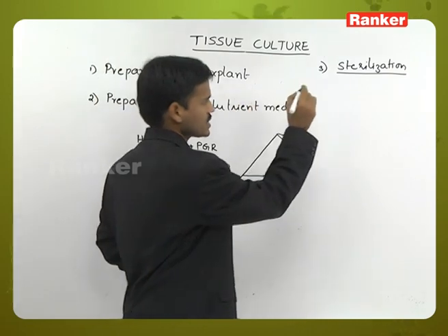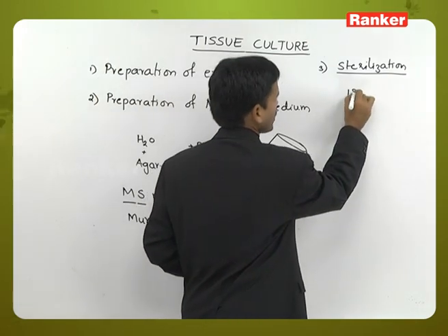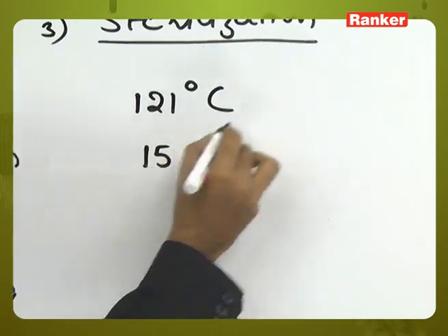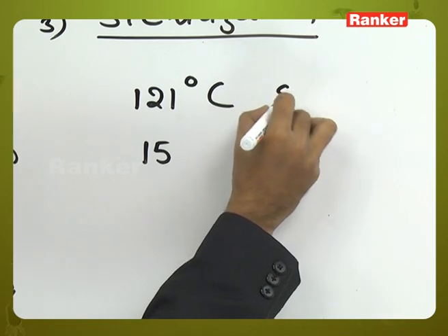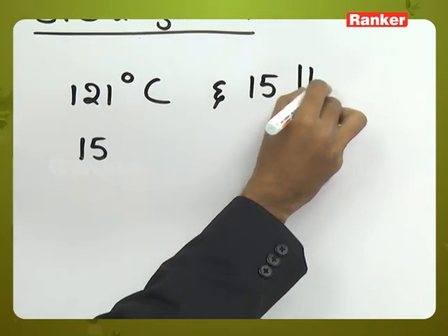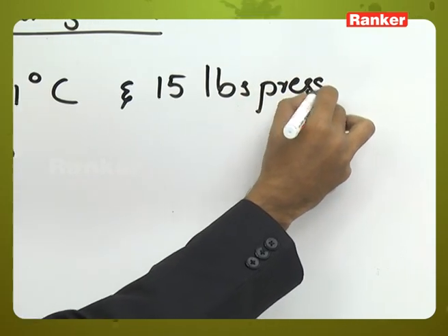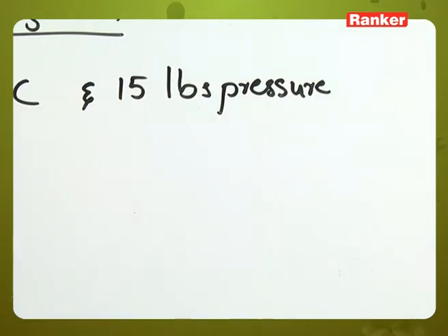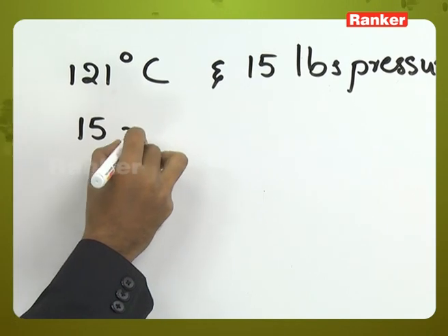So, the sterilization is carried out at 121 degrees centigrade and 15 lbs pressure for 15 minutes.